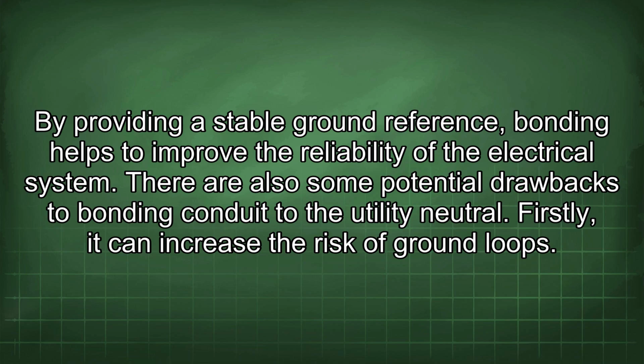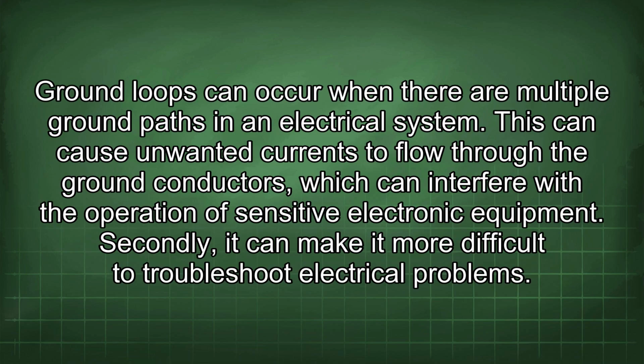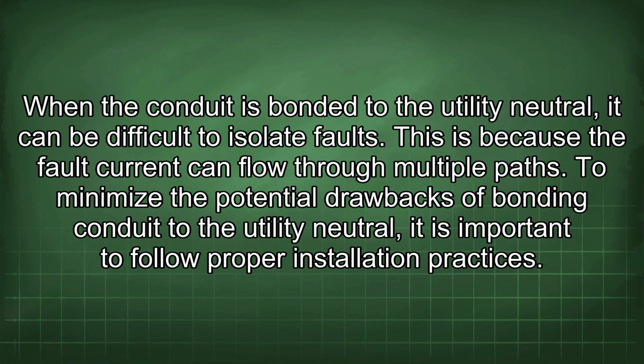There are also some potential drawbacks to bonding conduit to the utility neutral. Firstly, it can increase the risk of ground loops. Ground loops can occur when there are multiple ground paths in an electrical system. This can cause unwanted currents to flow through the ground conductors, which can interfere with the operation of sensitive electronic equipment. Secondly, it can make it more difficult to troubleshoot electrical problems. When the conduit is bonded to the utility neutral, it can be difficult to isolate faults. This is because the fault current can flow through multiple paths.